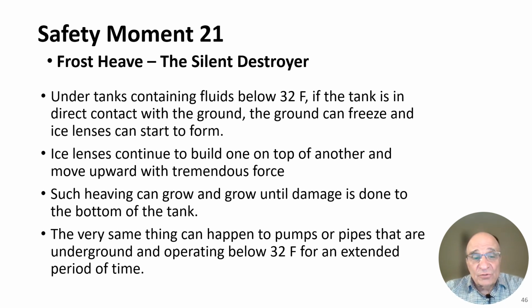So you want to make sure that you don't have frost lenses, ice lenses, building up underneath your tank. And we'll talk about how those are avoided. Such heaving can grow until there is damage done to the bottom of the tank, and you want to avoid that. And the very same thing can happen to pumps or pipes that are underground and operating below 32 degrees Fahrenheit for an extended period of time.